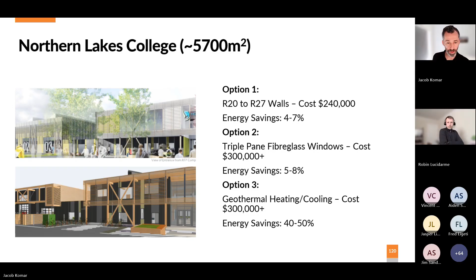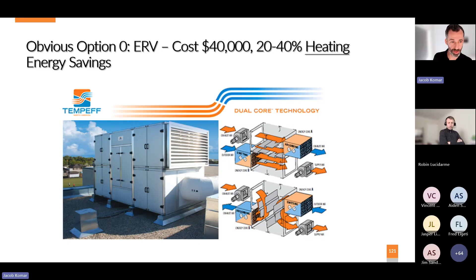What we found is once we picked the Geo system, upgrading walls from R20 to R27 only made a 0.8% energy difference. All of a sudden, the envelope upgrades made zero sense. The first thing you always need to do is recover heat from your fresh air system, so ERVs are absolutely crucial with geosystems.